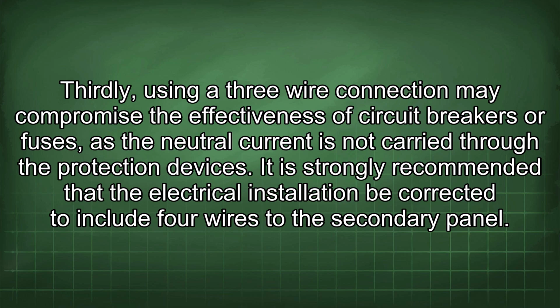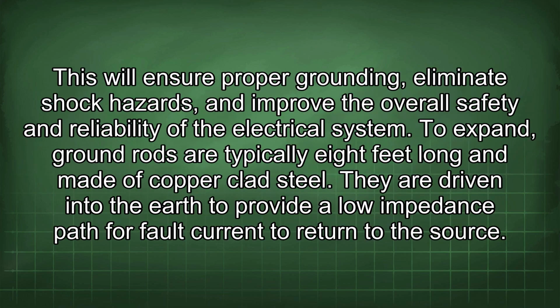It is strongly recommended that the electrical installation be corrected to include 4 wires to the secondary panel. This will ensure proper grounding, eliminate shock hazards, and improve the overall safety and reliability of the electrical system. To expand, ground rods are typically 8 feet long and made of copper-clad steel. They are driven into the earth to provide a low impedance path for fault current to return to the source.